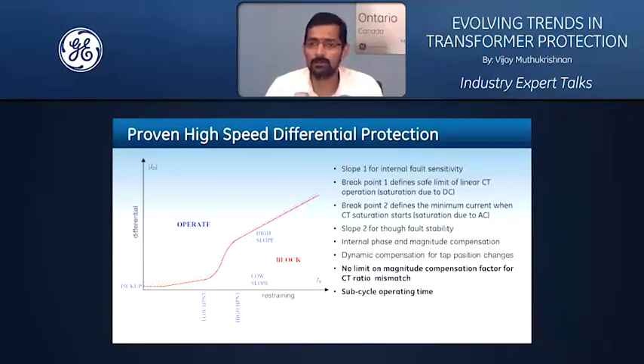Now, what you expect out of this type of transformer relay is internal phase and magnitude compensation. You expect dynamic compensation for tap changer positions. And it will be ideal if the transformer protection relay does not impose any limit on the magnitude compensation factor for CT ratio mismatch. On top of all this, if you can get a subcycle operating time for certain fault conditions, that will be really awesome in terms of the speed of operation you expect from your transformer protection relay in order to isolate internal faults.